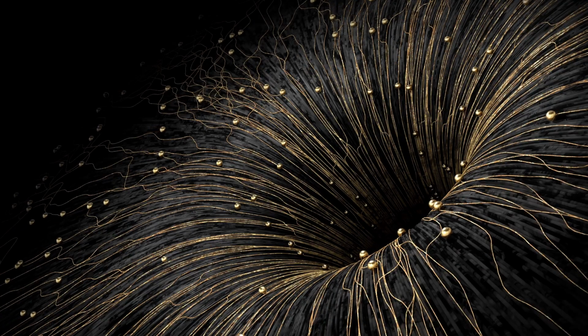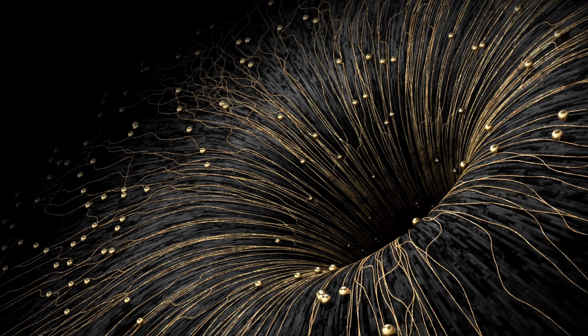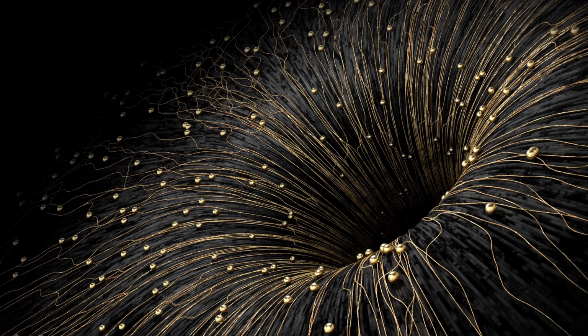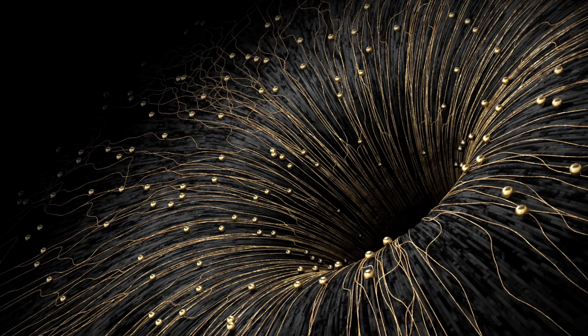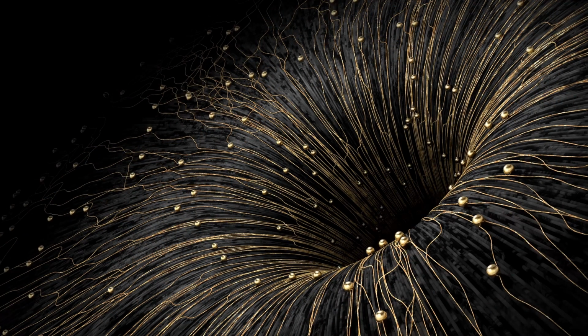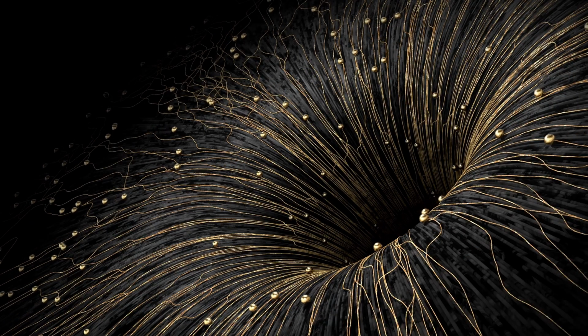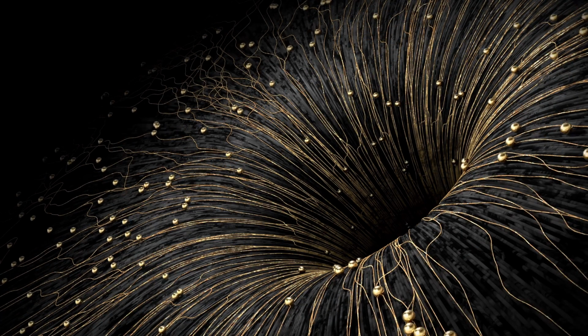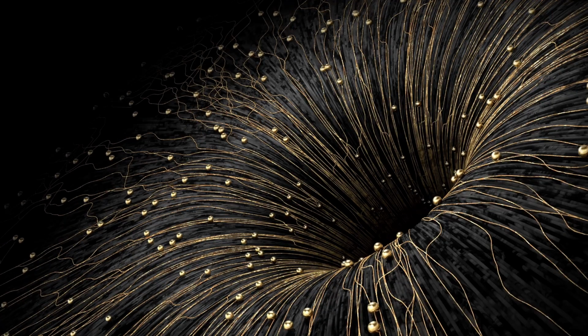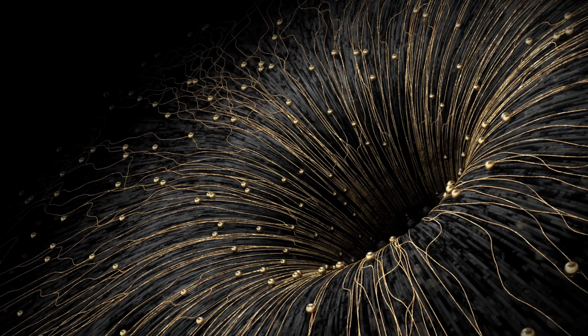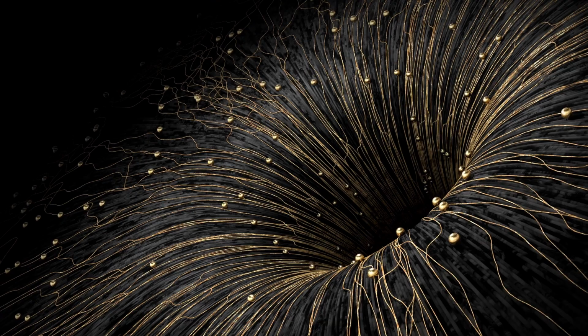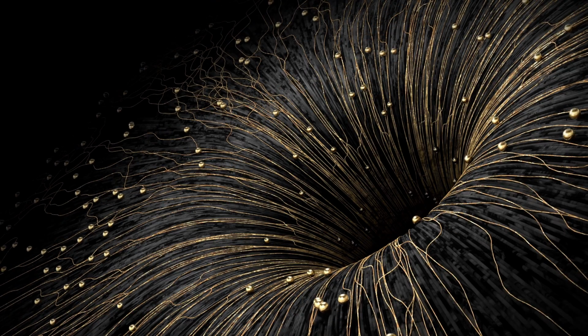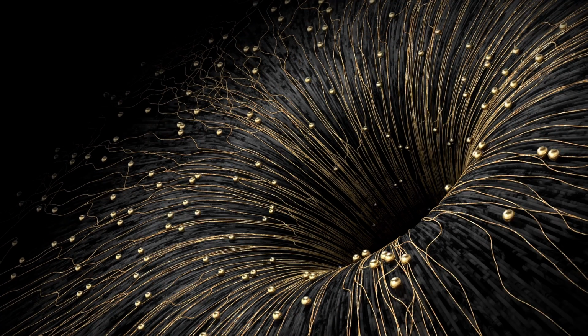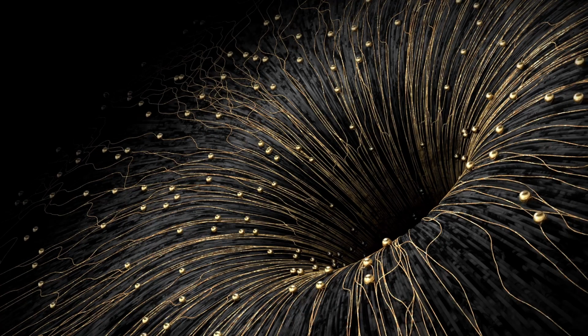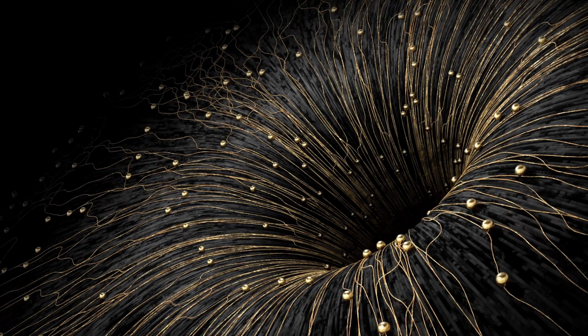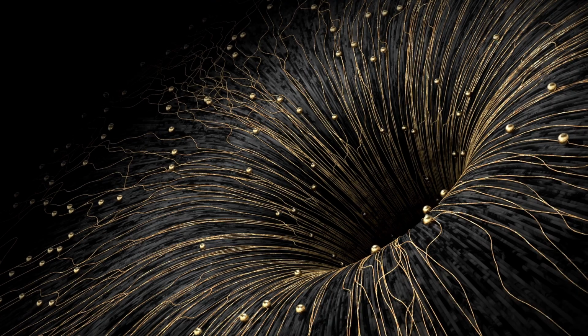It is a valid, literal question. The heat generated by that density of silicon is enough to physically melt standard server components, solder, and plastic in a matter of minutes if the cooling fails. Air cooling, using fans to blow chilled air over metal heat sinks, is completely obsolete at this level, you literally cannot move enough air fast enough. You have to use liquid, because it has a drastically higher specific heat capacity than air and absorbs heat vastly more efficiently.